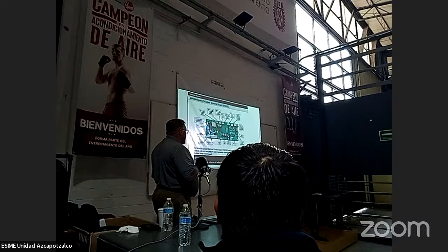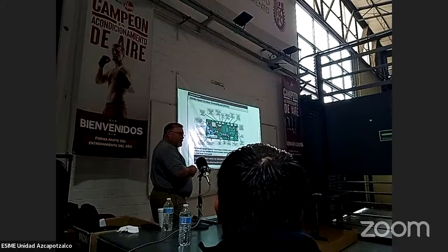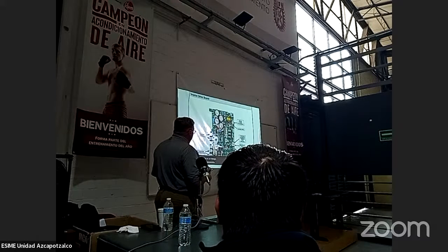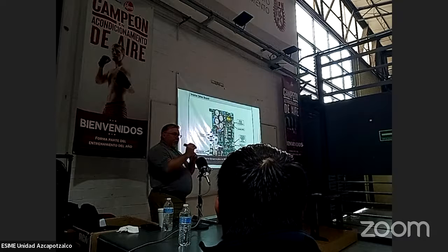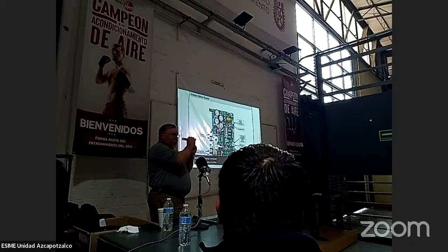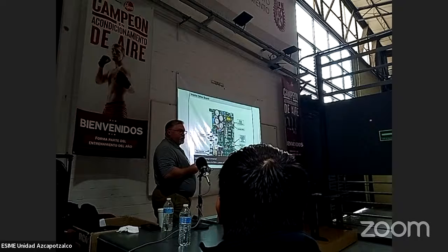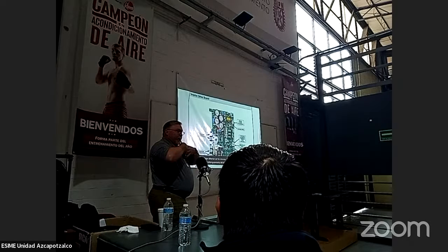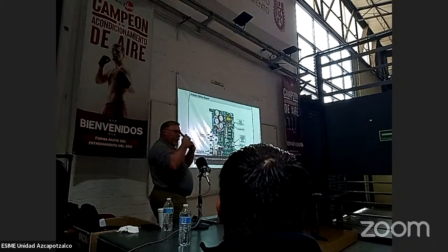Variable speed outdoor control board manages the functions of the outdoor unit and handles the communication between the outdoor unit and its smart thermostat. Okay? That's its job. On the drive board, a few things to know. Remember, I told you that your filter board powers in here, so if you're checking power incoming and you check it at the filter board and you go through on that filter board, when you get to here, all of those voltages should be the same. Okay? You also have the choke that we talked about that is monitoring electrical spikes, that actually absorbs those spikes. This is where that plugs into the board. Okay?